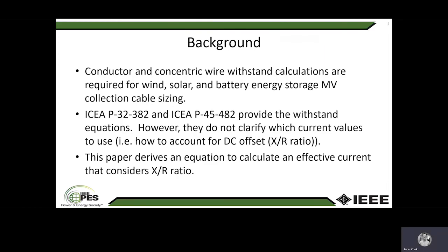As far as background here, any renewable energy project these days, whether it's wind, solar, or battery energy storage, it's necessary to perform conductor and concentric wire short circuit withstand calculations for the medium voltage collection system cable. This is done in accordance with these two ICEA standards here. One of these deals with the phase conductor, and the other deals with the concentric wire.